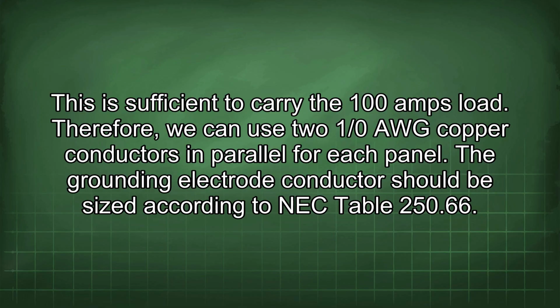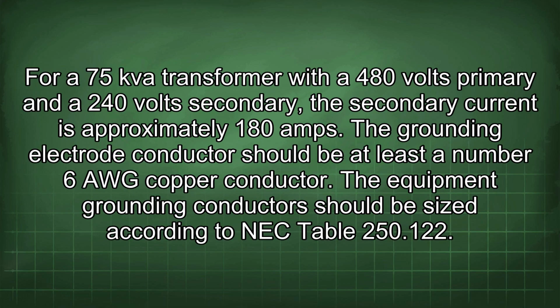The grounding electrode conductor should be sized according to NEC Table 250.66. For a 75 kVA transformer with a 480 volt primary and a 240 volt secondary, the secondary current is approximately 180 amps. The grounding electrode conductor should be at least a number 6 AWG copper conductor.